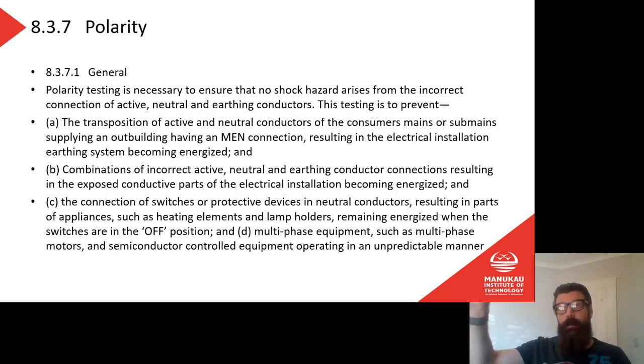Think about it. The phase coming in gets connected to the neutral part of my installation instead of the phase. It's actually transposed. That neutral is connected to the earth. The earth is connected to all of the metal parts in my building. So now my metal kitchen bench is connected directly to the phase. This is very bad, very, very bad. And it's easy to do.